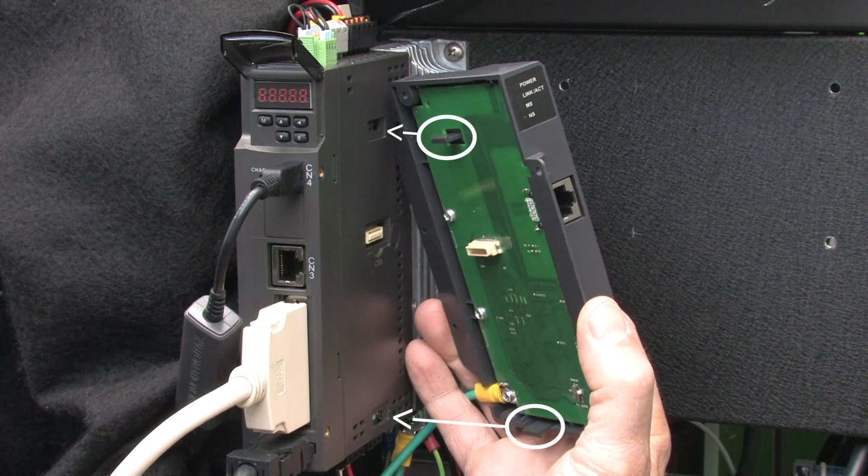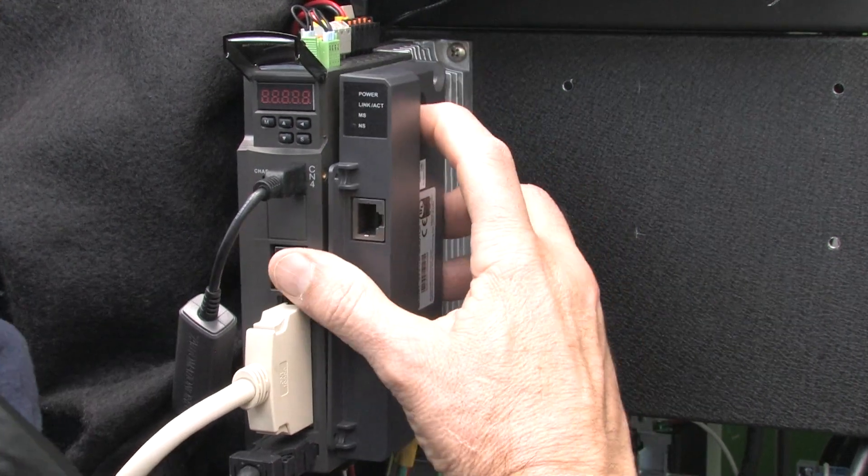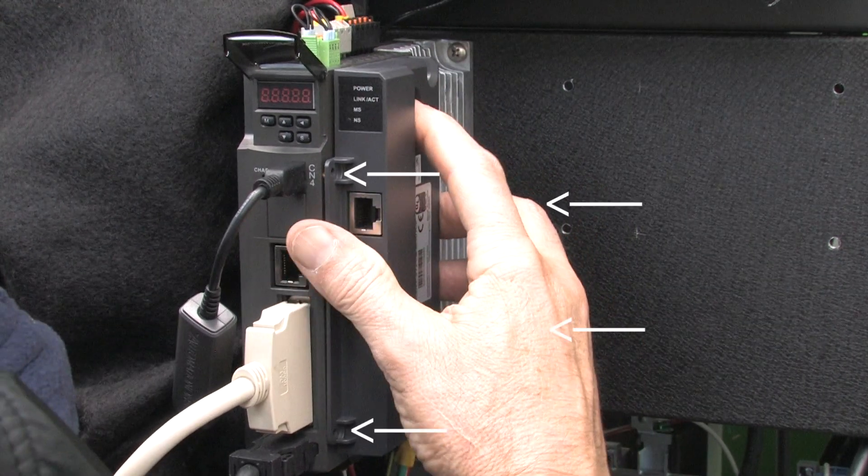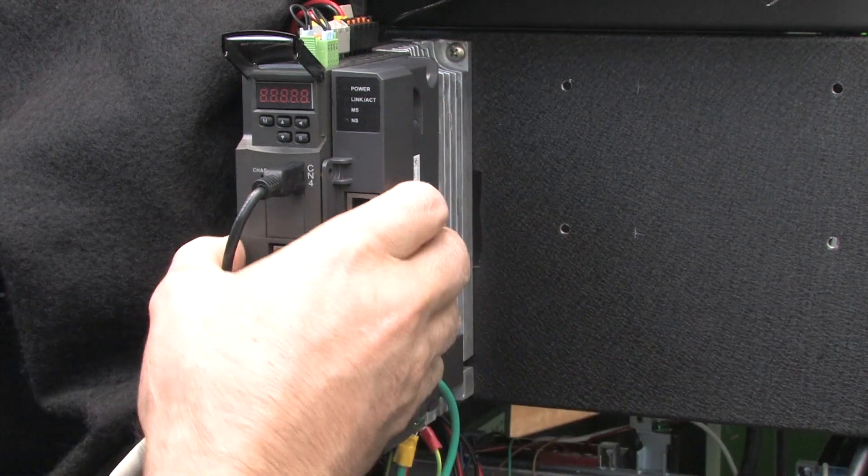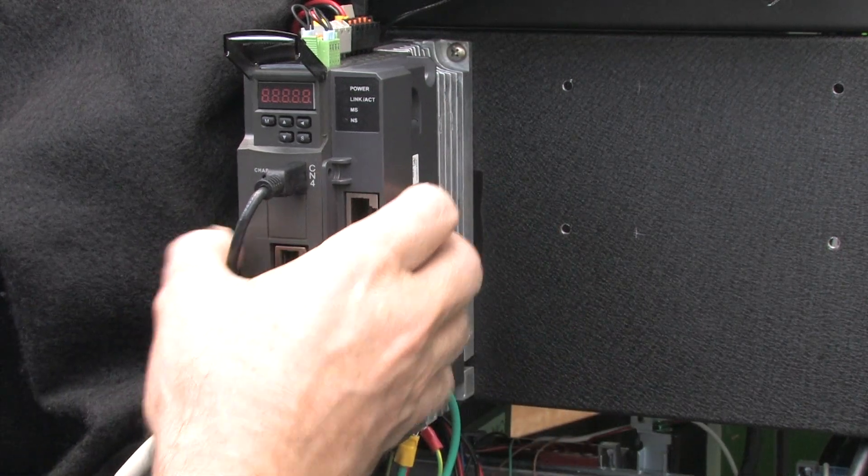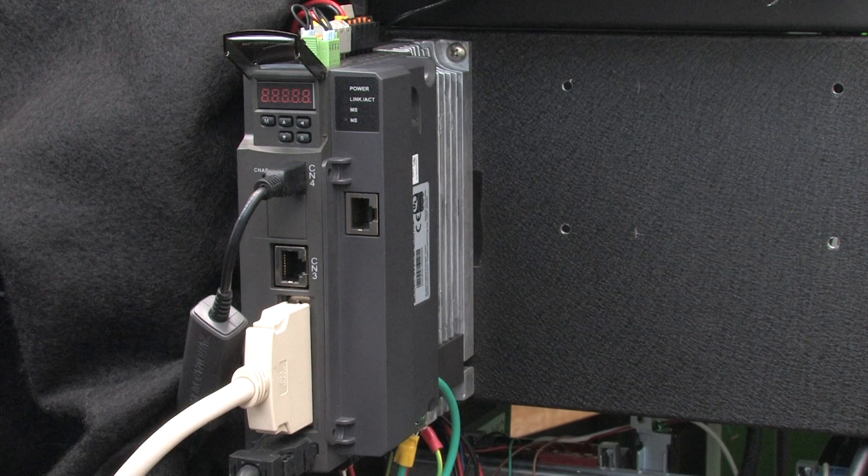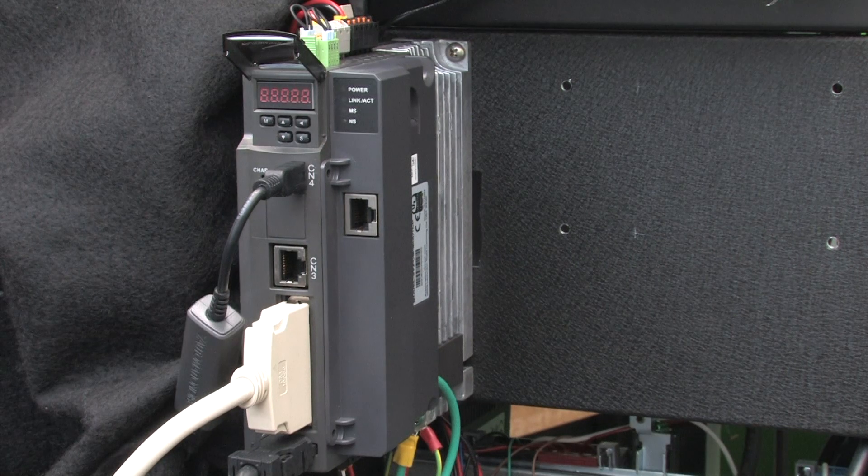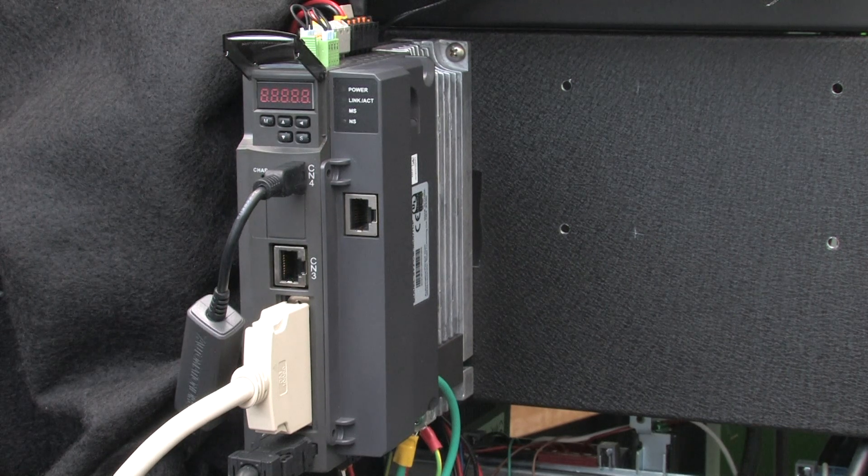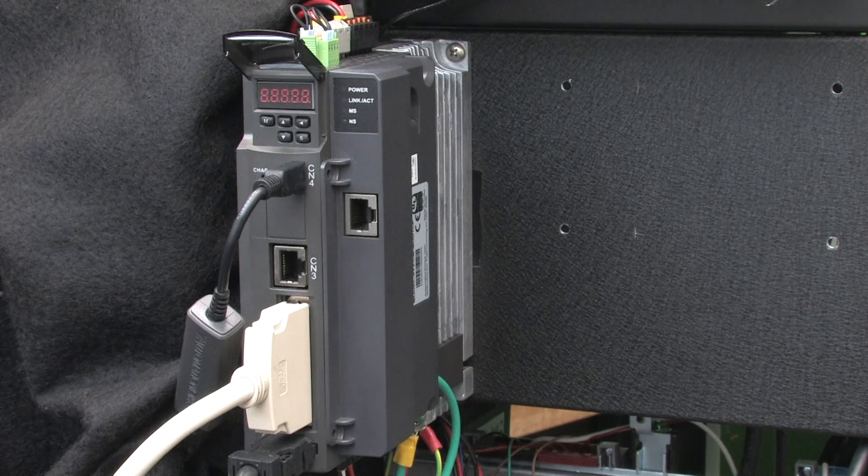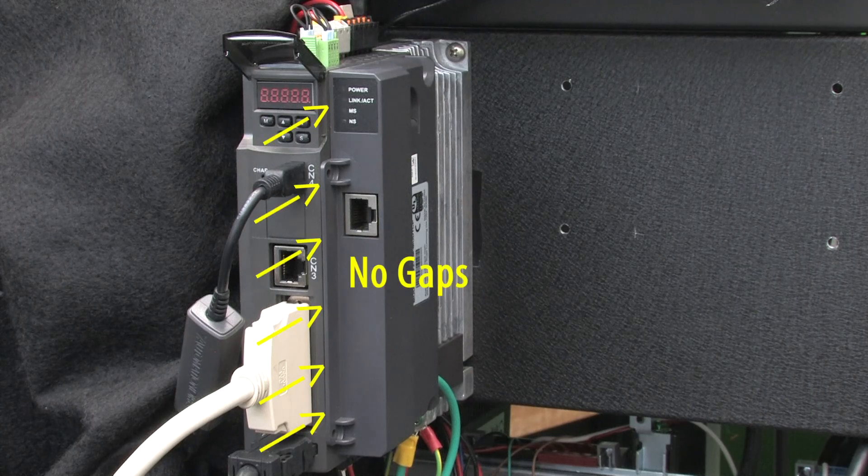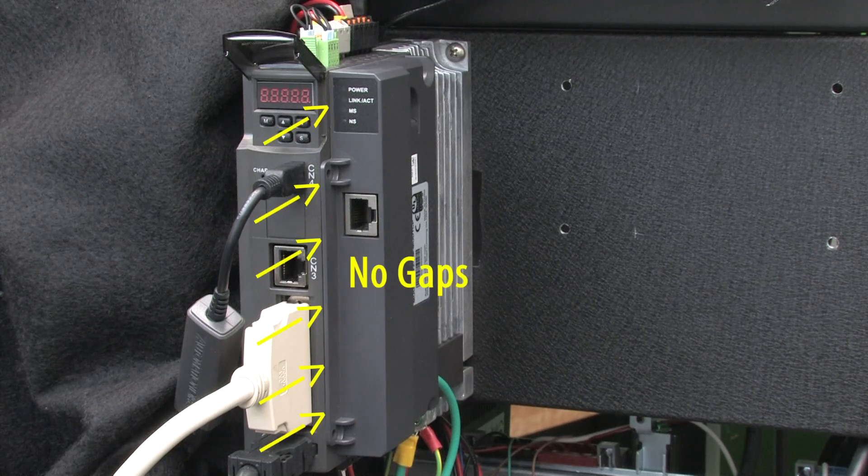Carefully align the clamping tabs into the matching slots. Double check that the four mounting holes are aligned and then press the COM card into the drive. If it feels like it's taking any force at all, then back off and double check the alignment. It will easily drop into place if it's aligned correctly and there will be no gap between the drive and the module.